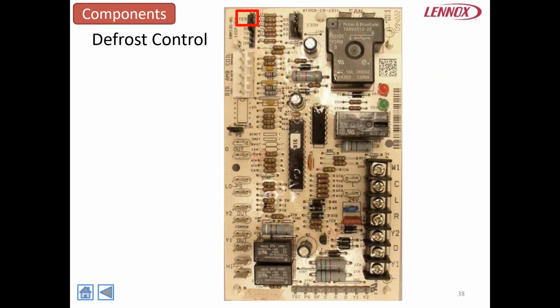All right, we're going to talk a little bit about the defrost control here. The XP16 and up, we talked about it uses the demand defrost, which measures differential temperatures to detect when the system is performing poorly due to ice buildup on the outdoor coil. The control self-calibrates itself when it starts and after each defrost cycle. So it's always learning what's going on. It monitors outdoor ambient temperature, the outdoor coil temperature, and total runtime to determine when defrost is required. Okay, so you'll tend to see a little heavier frost on this system than a normal system.